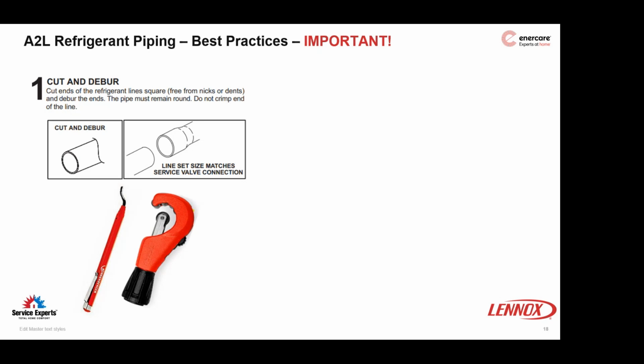And then, if for some reason you're connecting 3/4 inch pipe to a 7/8 or 1 1/8 connection, make sure you're using the appropriate reducing or increaser fitting. We're not pinching or crimping piping or fittings to make them fit and then brazing around them. We use the appropriate fittings to maintain pipe integrity and joint integrity. Before brazing the joints, inside and out, remove any Schrader cores and caps to prevent damage from the heat of the torch.